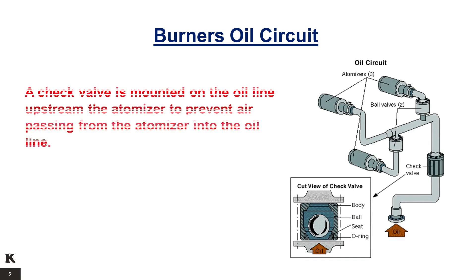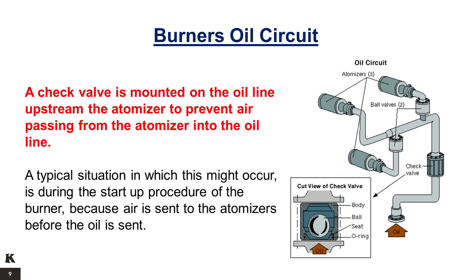Burners Oil Circuit. A check valve is mounted on the oil line, upstream of the atomizer, to prevent air from passing from the atomizer into the oil line. A typical situation in which this might occur is during the start-up procedure of the burner, because air is sent to the atomizers before the oil is sent.